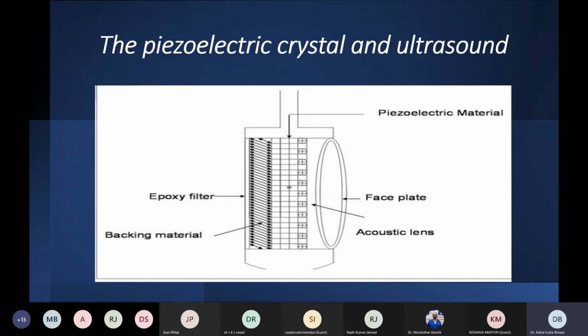Now, these piezoelectric crystals in modern echocardiography probes are put in multiple ways. So, in the beginning years of echocardiography, there used to be linear array probes. So, there were one or two piezoelectric crystals, very simple machines. You had to move the transducer to face a particular region, a particular field of interrogation. The breakthrough in medical ultrasound came with the phased array, where the piezoelectric crystals are placed in such a way that we can command them to trigger signals in particular sequences. So that is why when you move the multiplane probe from 0 to 180 degree, this phased array piezoelectric crystals can exactly send out sound waves according to the area that where you want to focus. So it is a marvelous modern technology.